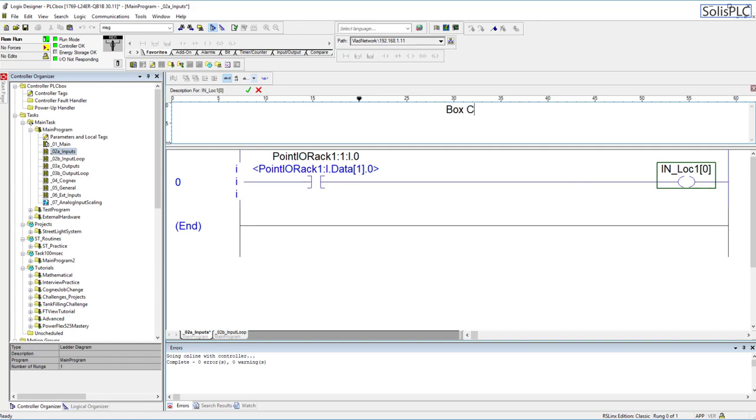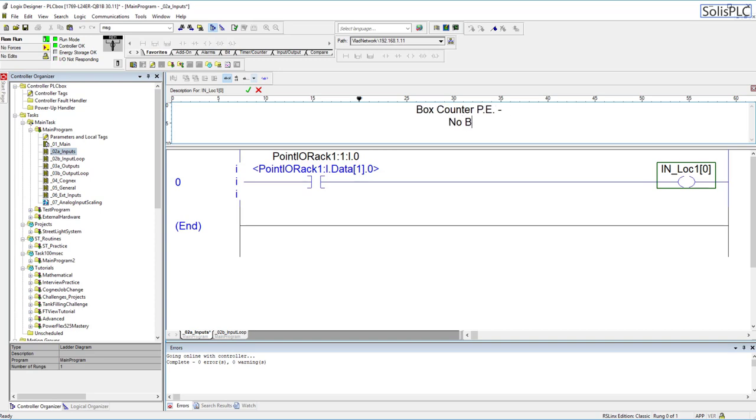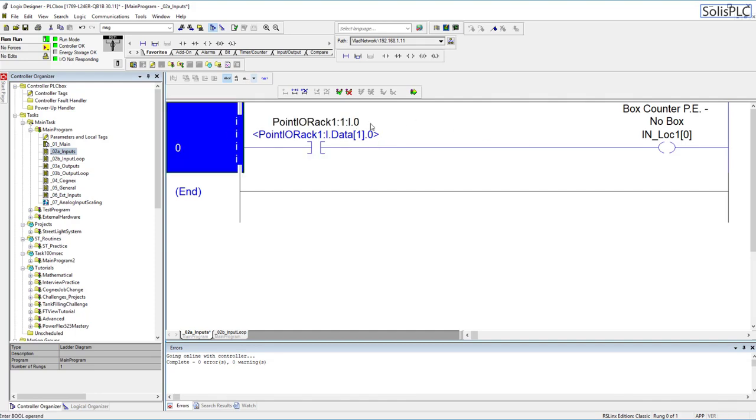This is going to be our box counter photo eye PE. The way you set this up is that you will tell the PLC with the state when the sensor is actually flagged. When the sensor is flagged that means there is no box in front of it, so no box. What I mean by that is essentially the tag is going to be high when there is no box because we have our reflector on the other side of the sensor.